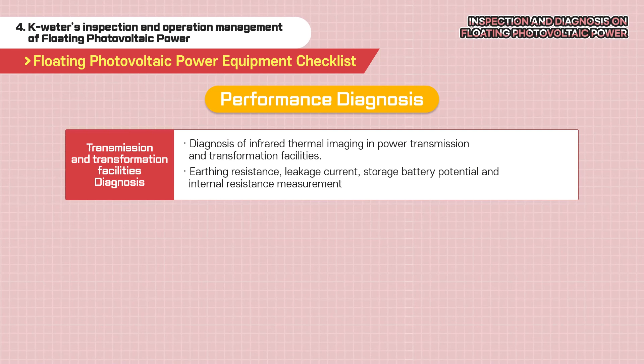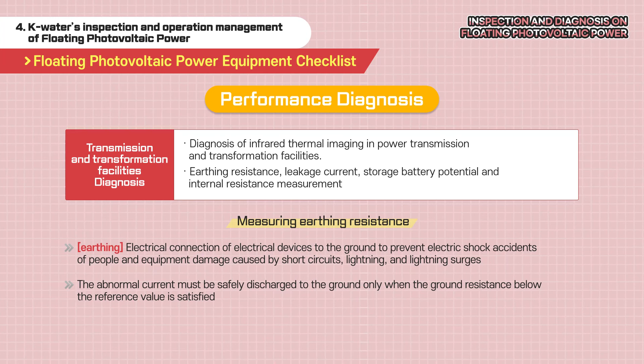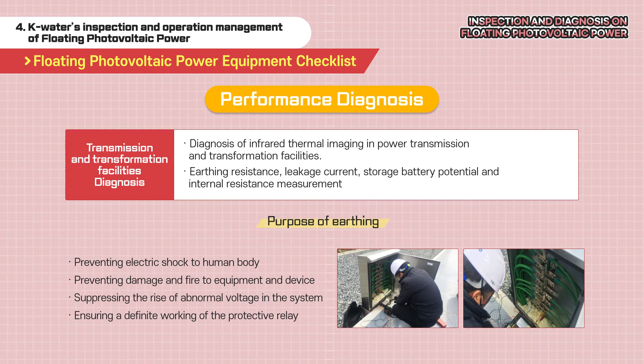Earthing refers to electrically connecting electrical devices to the ground to prevent human electric shock, accidents, and facility damage due to leakage current or lightning surges, and must meet the ground resistance below the standard to safely discharge it to the ground. The earthing resistance measurement is to determine any abnormalities by measuring quarterly whether the devices of the power transmission and transformation have a ground resistance value below the reference value and analyzing the data trends.